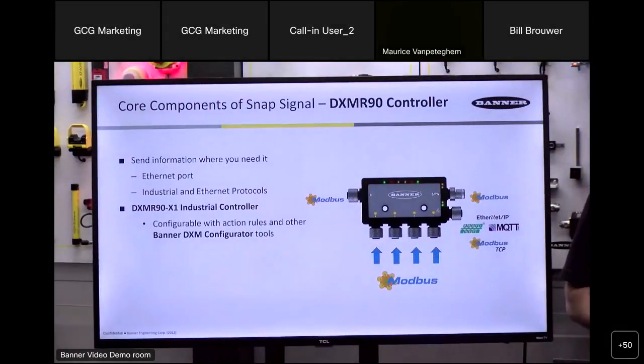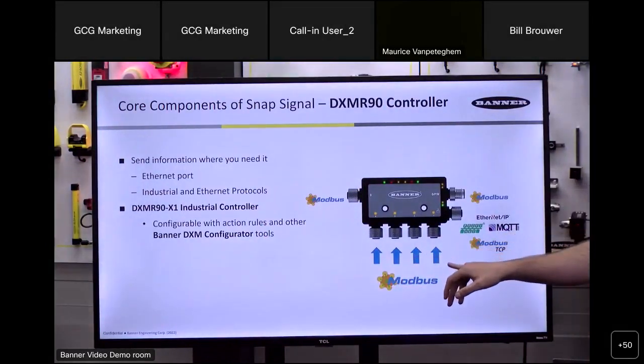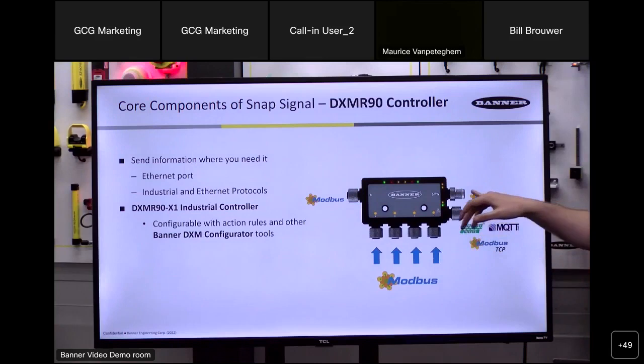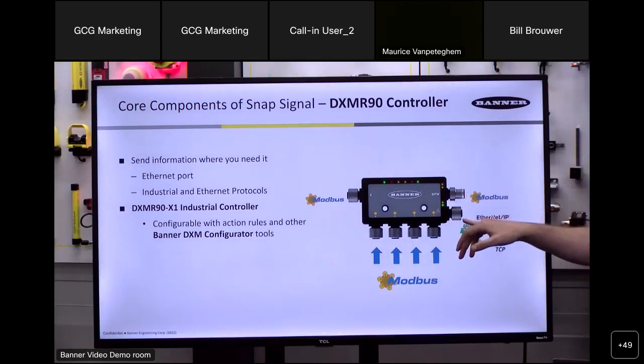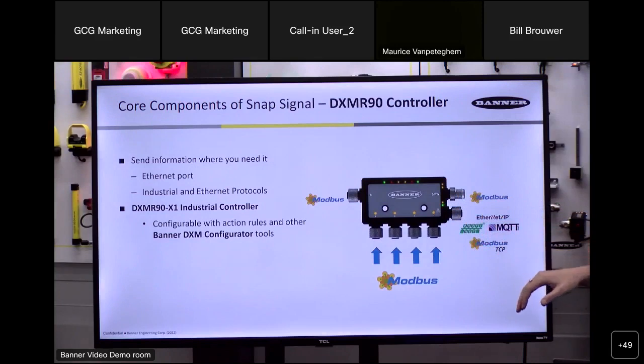The DXMR90, again, I like to think of this product as the consolidator. You have the 4 individual Modbus master ports, or Modbus client ports, at the bottom. You have power on this M12 connector here, and you also have this dual industrial Ethernet port that sends the data out to the world via EtherNet/IP, Profinet, Modbus TCP, or via MQTT to cloud platforms, for example.